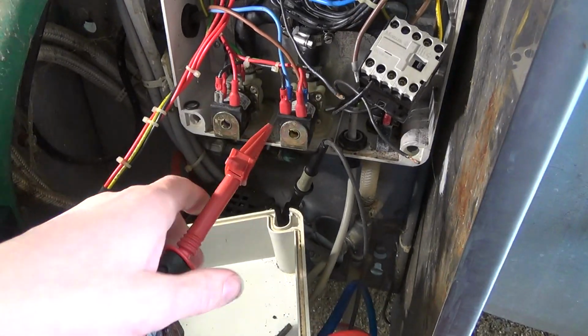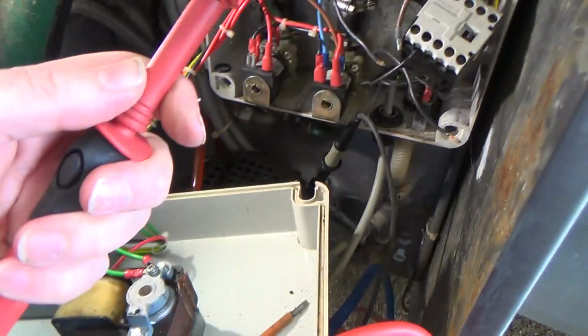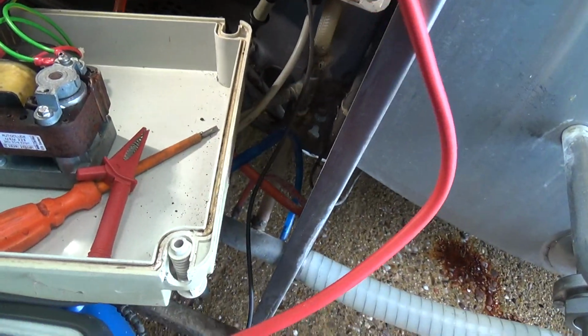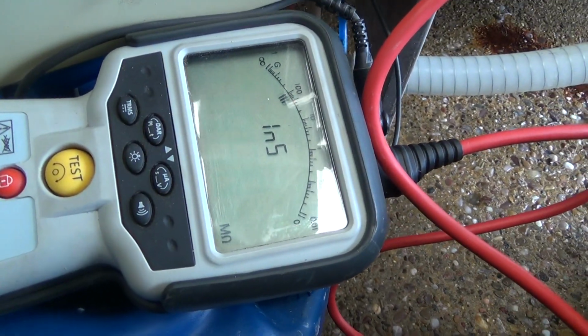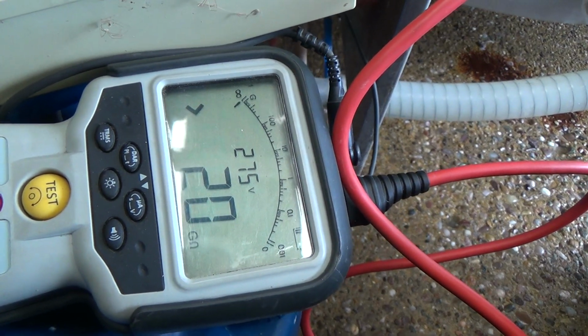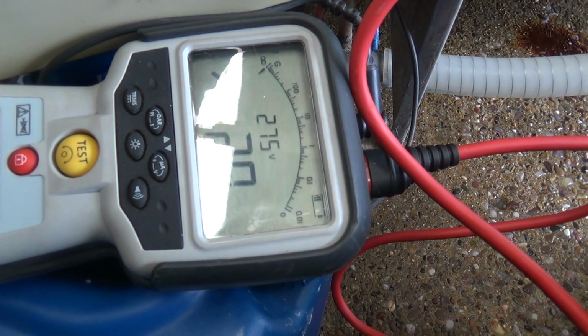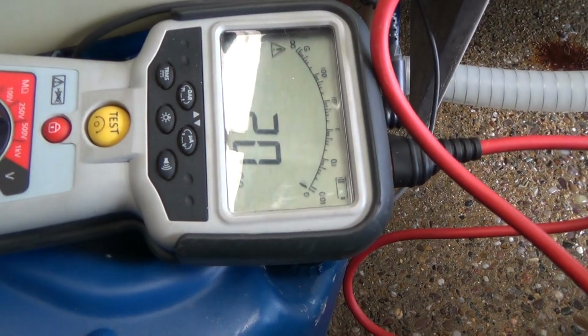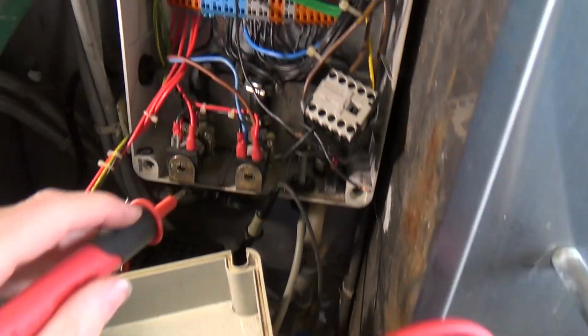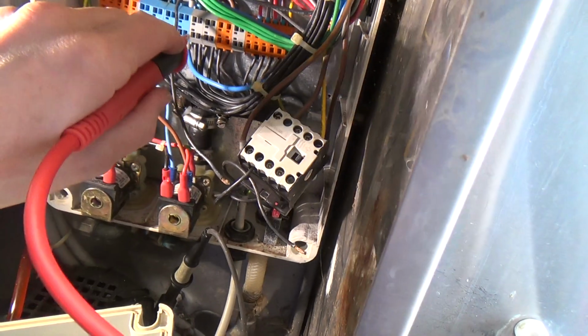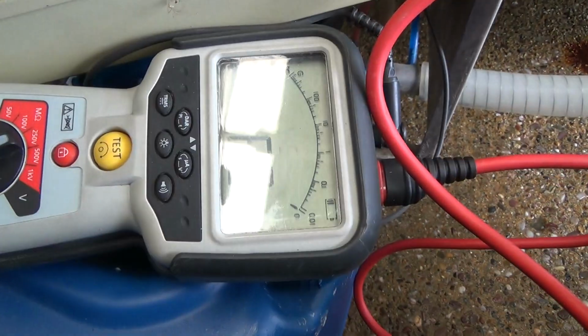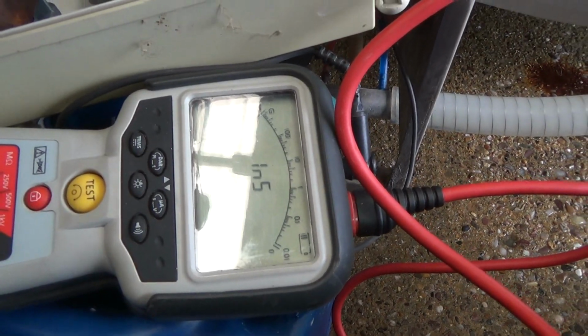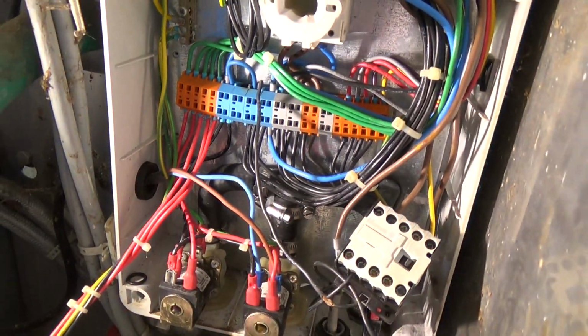Right, I wonder what else it could be? Let's take this off. Let's go on here. Okay, that's our coil. That's our incoming live, 20 gigaohms. That's our outgoing live, 15 gigaohms. Is this shorted here? Now this test probe might not reach in enough to touch there, because you need a very fine probe to get the little holes.